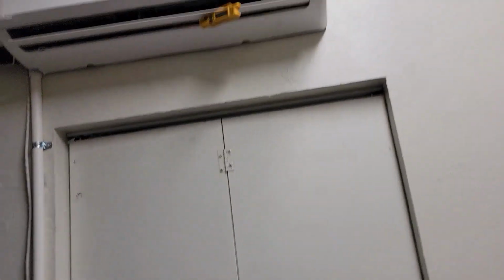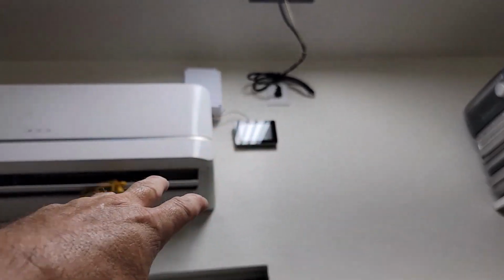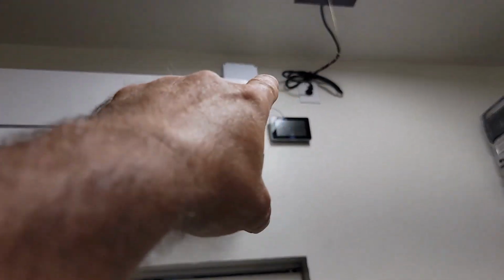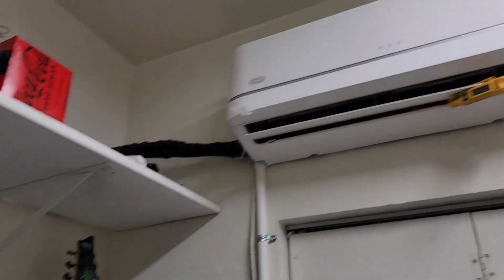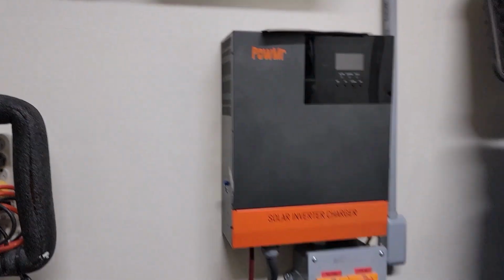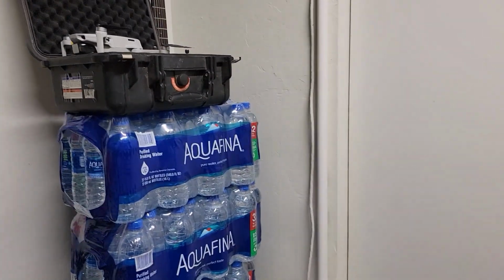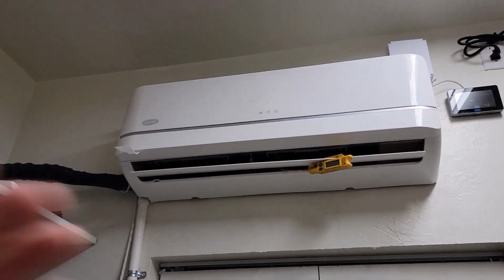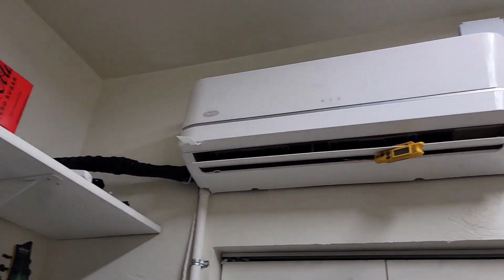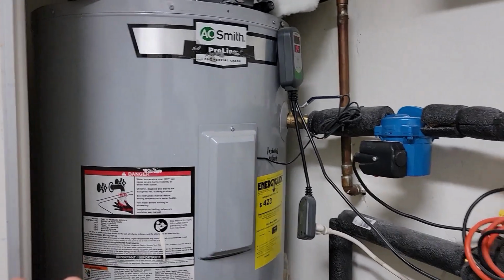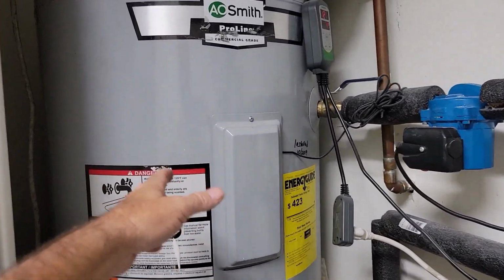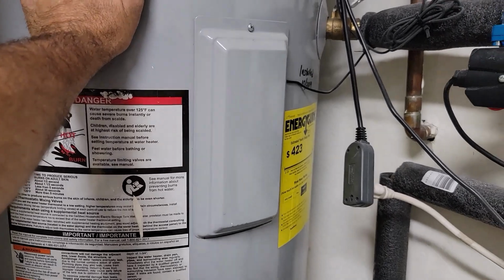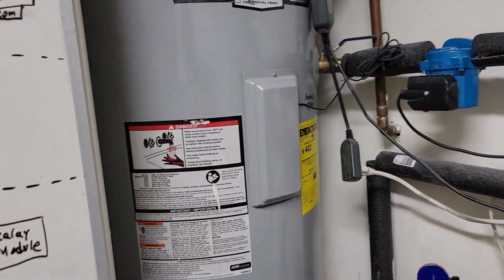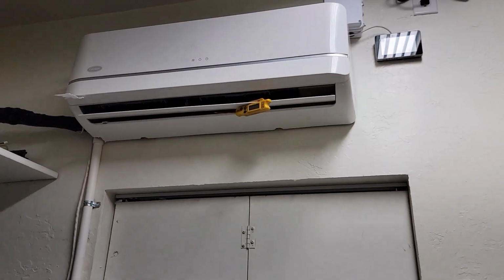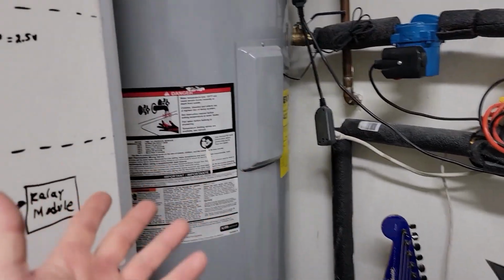I need to have two inputs, like a 2-stage thermostat. I have the one up there that's hooked up to this with my own 24-volt little controller up there, and then this one, and basically working together, my main control needs to decide which coil to use for the evaporator, the indoor one or the outdoor one. It also has to have a high limit for when this water gets too hot. I can probably easily heat this water to 150, and there might be summer days where if I run the cooling a lot, maybe it will get that water to 150.